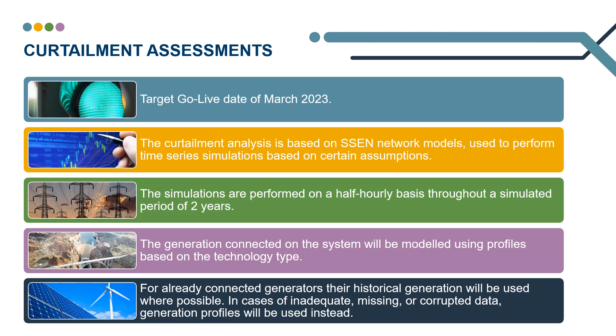Once the process is concluded, it will be sent out to the customer in the form of a feasibility study. The simulations are performed on a half-hourly basis throughout a simulated period of two years using historical data. For already connected generators, their historical generation will be used where possible. In cases of inadequate, missing, or corrupted data, generation profiles will be used instead. For the customer that is applying, if they have a bespoke or known profile, that can be provided to SSEN to use within an assessment. Otherwise, a generic profile for that technology type will be used.